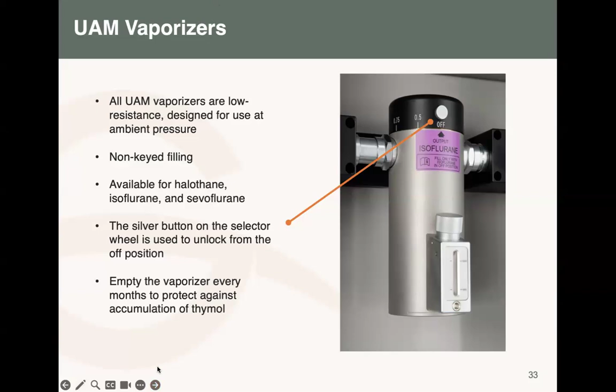But always remember to empty the vaporizer now and then. Of course, you have to use it all the way, maybe when it's almost down near the empty line, then you can drain it so that you can remove the thymol. This depends on how busy you are, but it should be done at least every month. Some sites that are not busy can go up to two to three months, but we advise monthly. Next.